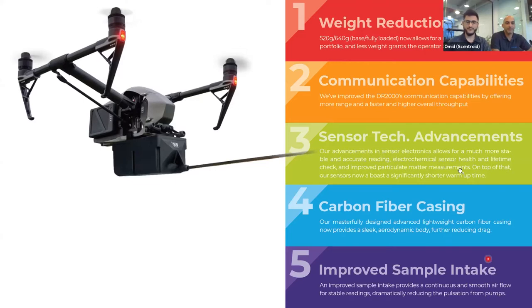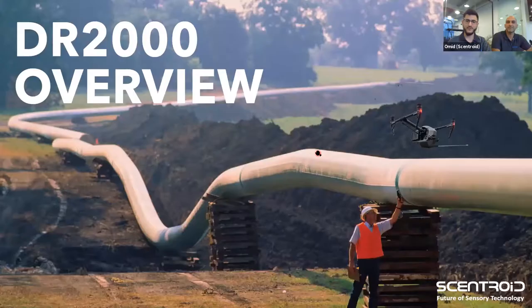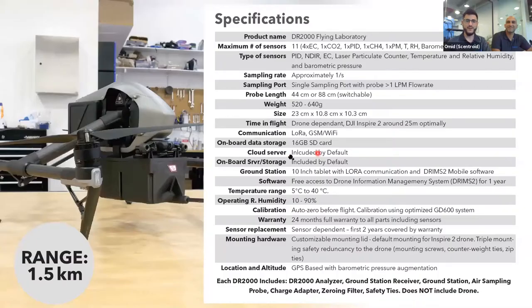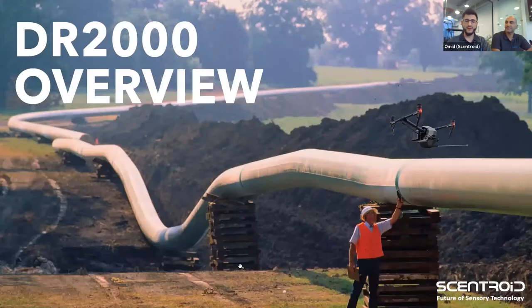Great, so our next question is: what is the lag time between the tip of the tube and an actual reading? That's a great question, which leads us to the next slide about the specifications of the product. Basically the delay is very small because the sample comes in at a rate of 2 liters per minute, so it reaches the sensors very fast, and the sensors typically have a response time of a few seconds. So it's just a matter of seconds before the sensors respond.